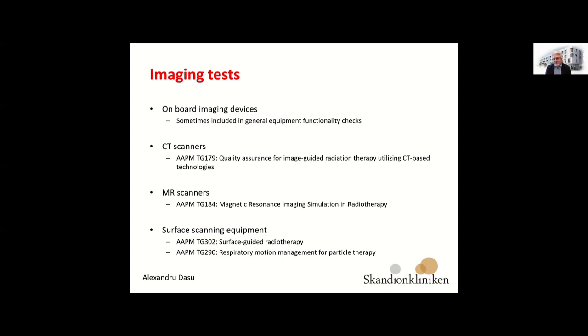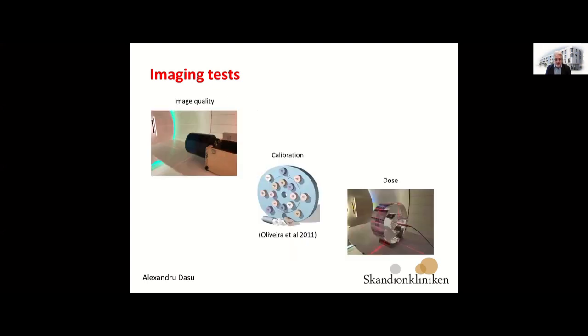Imaging: there is a lot of imaging in modern radiation therapy. You have onboard imaging devices that you use for checking the positioning of the patient. They are sometimes included in general equipment functionality checks, but you also have the CT scanners, the MR scanners, and surface scanning equipment. All of these are used to ensure that the patient is correctly positioned during the treatment. There are not unexpected recommendations on all these aspects from the AAPM, which are very good. If you work with this, I recommend that you read them and get inspiration about what could be achieved from a good quality assurance in radiation therapy.